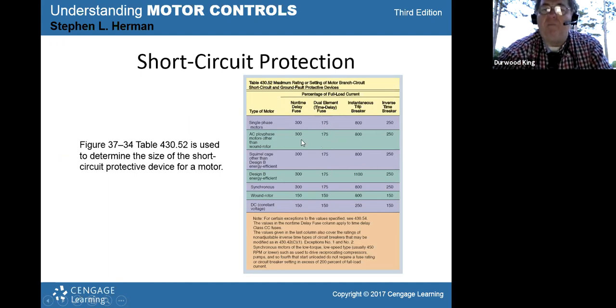So if you got a 3-phase motor, they call it polyphase. You can rate your fuse above the starter at 175% of your motor current. So you can take your motor current times 1.75, and that would be the maximum fuse size you could use. You don't have to go that big on the fuse, but that's the maximum size that you could use on fuse sizes. That's actually above the starter. Now, the last column, if it's a circuit breaker above the starter, it's going to be an inverse time breaker, not an instant trip. You don't use instant trip on motors because they're going to trip all the time.